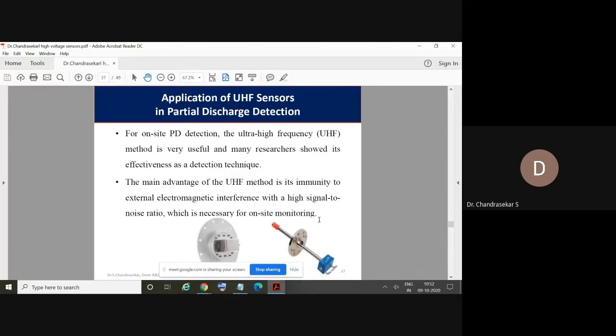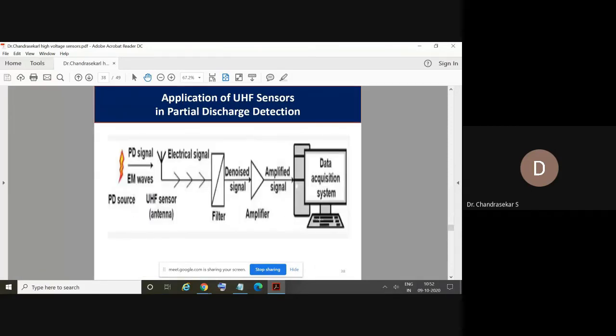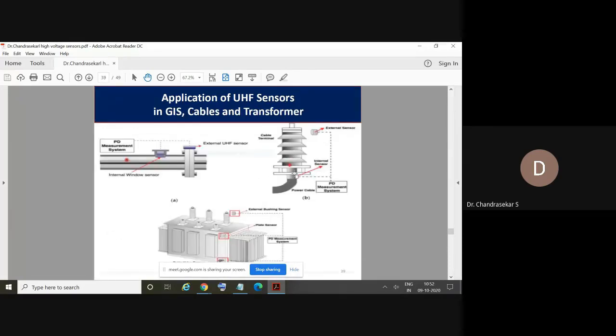As I already told, they have a very high immunity to external electromagnetic interference and also a very high signal to noise ratio. So this is a very basic block diagram which represents when the ultra high frequency antenna is there and it captures the PD signal, and it is converted to an electrical signal, and then it is filtered and denoised and amplified, and then it is given to the data processing system. So this is a very conventional flow.